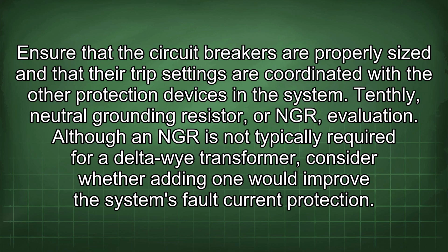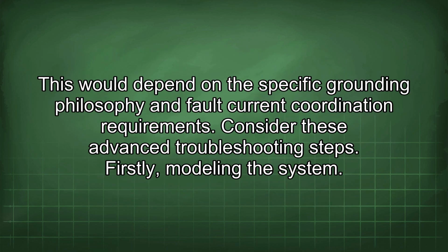Tenthly, neutral grounding resistor or NGR evaluation. Although an NGR is not typically required for a delta-Y transformer, consider whether adding one would improve the system's fault current protection. This would depend on the specific grounding philosophy and fault current coordination requirements.